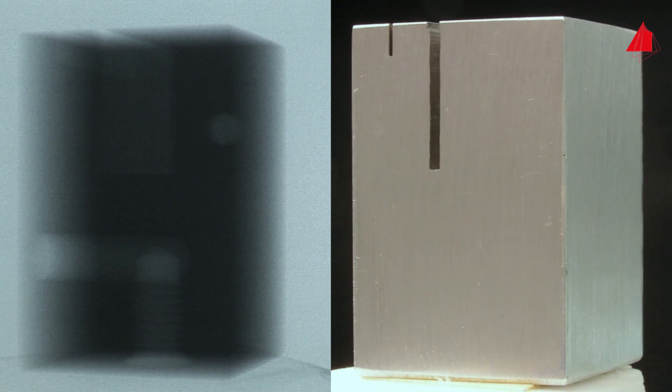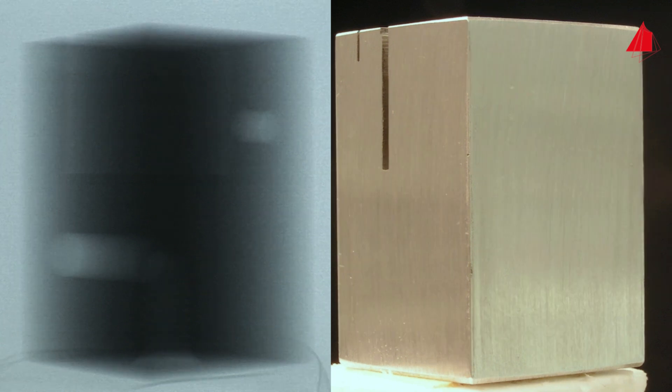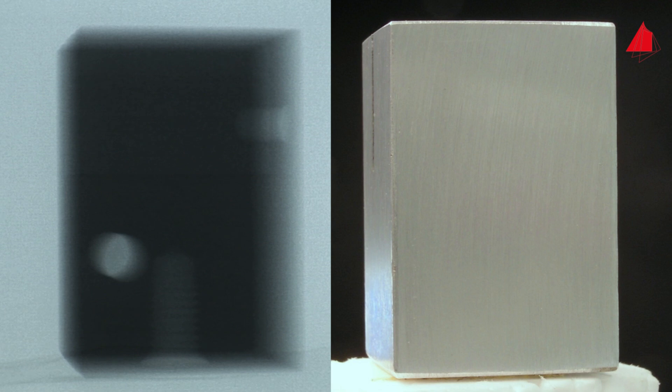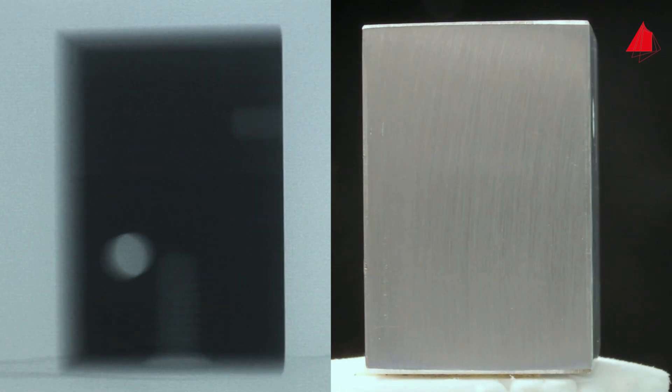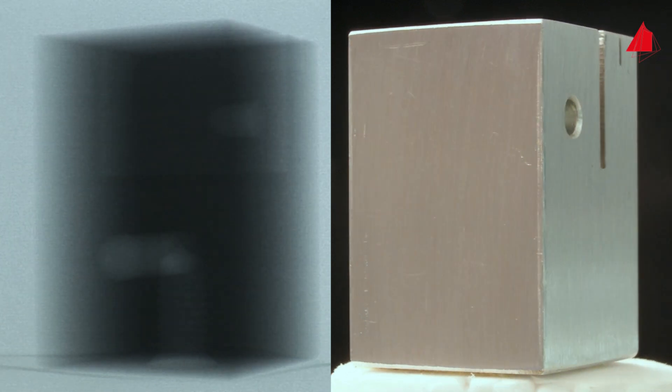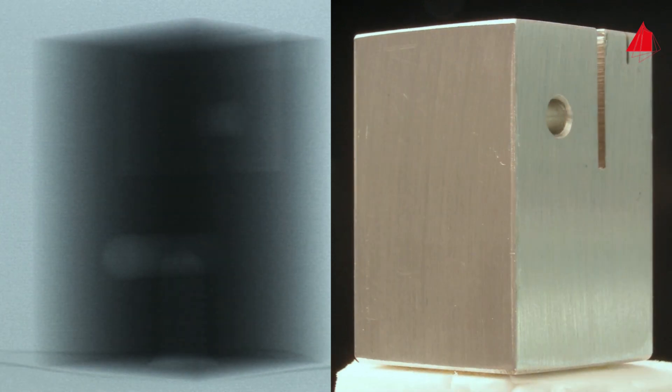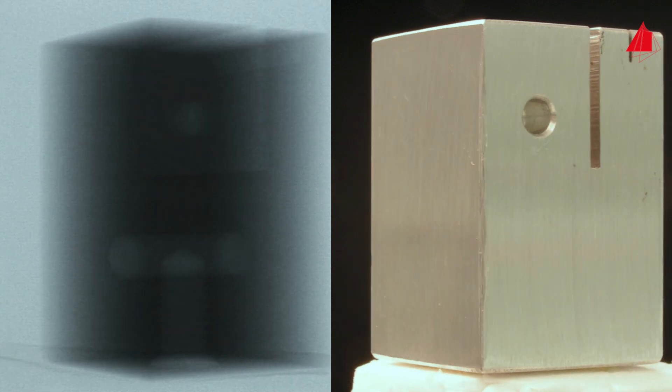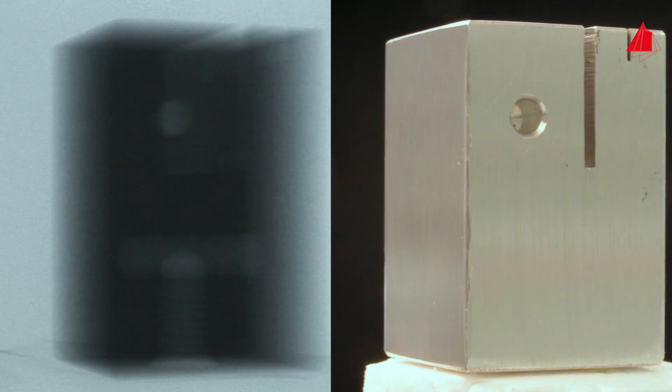In contrast to medical diagnostics, the x-ray tube and the detector field are both at rest and the sample rotates. The x-ray images are displayed in real time on the computer monitor. As opposed to classical x-ray images, they are shown as positive images. Thick areas and areas free from defects now appear dark. Thinner regions or regions with defects appear light. The drill holes and the different saw cuts are clearly visible.